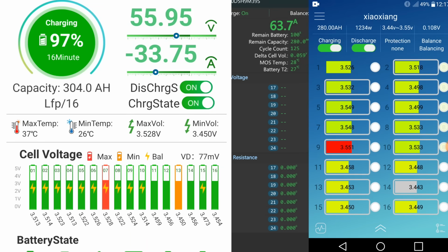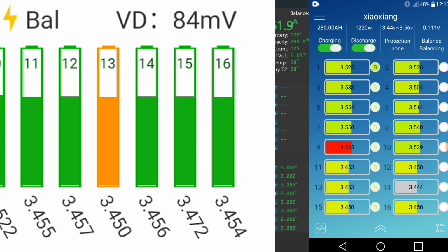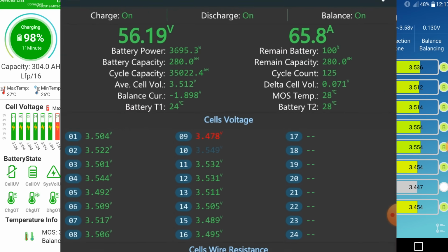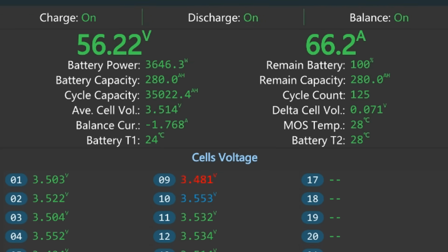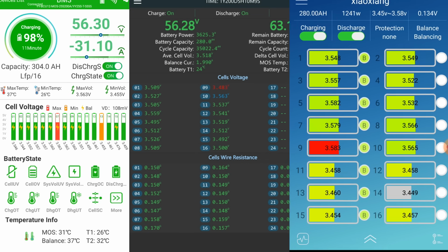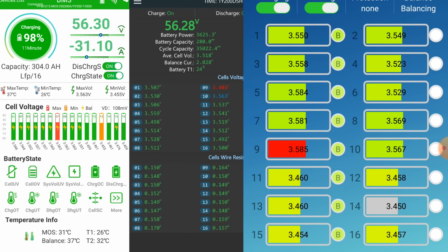The Heltec BMS in the top shelf is balancing cell number 1 to 10 plus cell number 15 now, with a deviation of 86 millivolts. The JK BMS in the middle battery is using its active balancer, with a deviation of 70 millivolts. The Overkill BMS in the bottom shelf is balancing cell number 1 to 13 now.